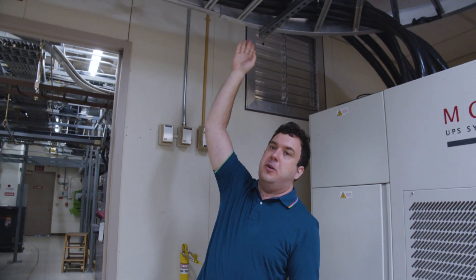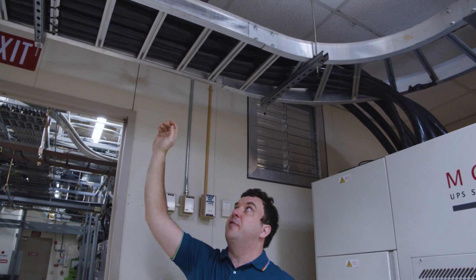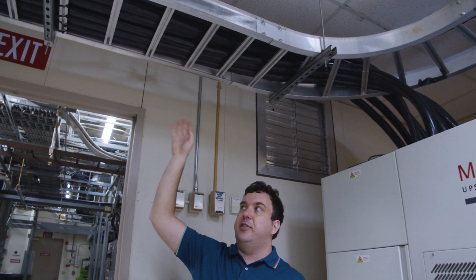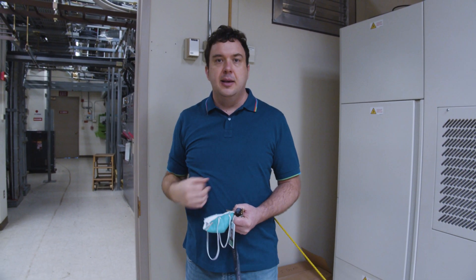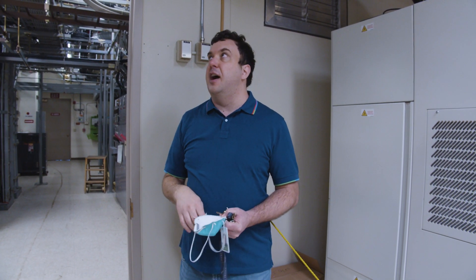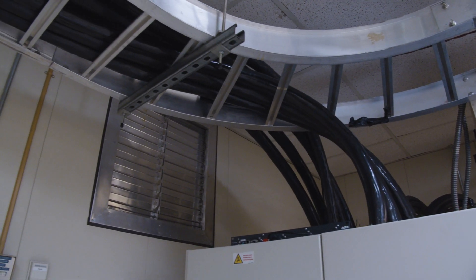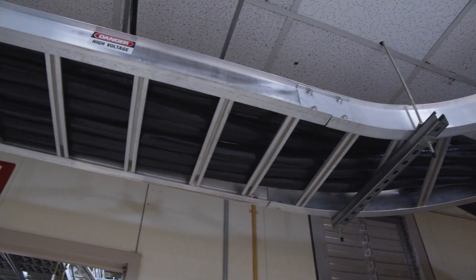This is 480 volt cables running in a tray. This is only allowed in a controlled environment where the cables aren't physically subject to damage. The reason we use it is it has a very low failure rate per foot, allowing us to operate with very high reliability without the failures you see with bus duct or cable in conduit where it gets scuffed. This allows us to visually inspect the cable, which we do on an annual basis with infrared cameras, and allows us to overlay more cables as needed.